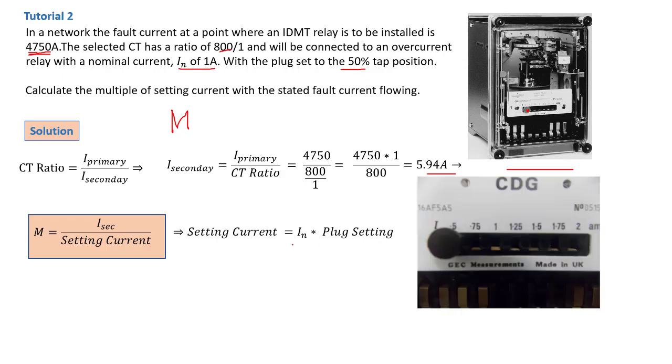In the previous tutorial, I explained the importance of your setting current as the function of the nominal current times the plug setting. As you can see right now here, the plug settings are set at 0.5, so that is now our setting current. Since we know the nominal current is 1 amp and the plug settings are set at 50%, that's basically 0.5.